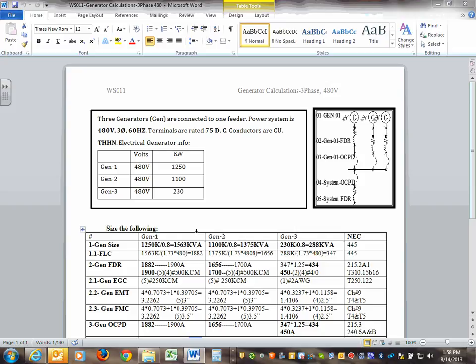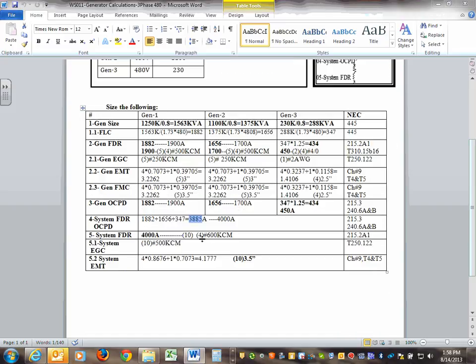The Square D Power Pact, I think, the first set point is 0.9, so you can't get to 3,900. You can't dial in anything more than 0.9. 3,900 is a larger number than 0.9. SKM PowerTools is supposed to know that. I found that, and I asked why PowerTools allowed me. It gets me to 0.9, because that's all you can do on that breaker. You have 0.9, and then it goes, because there's only like 16 indentations on it.